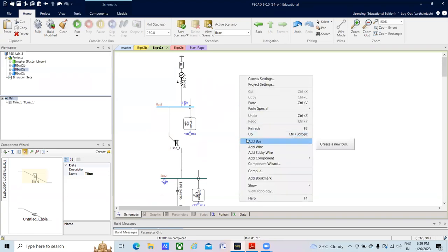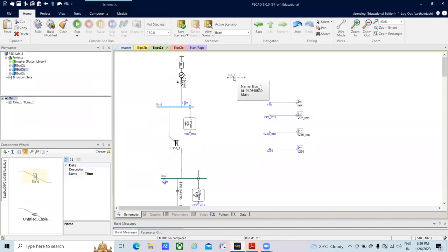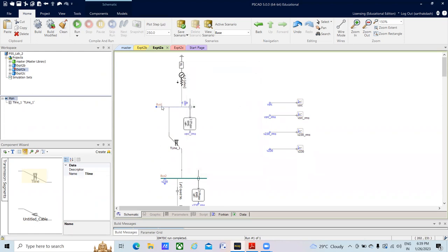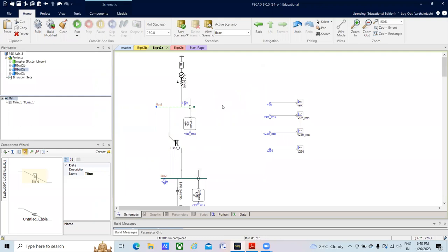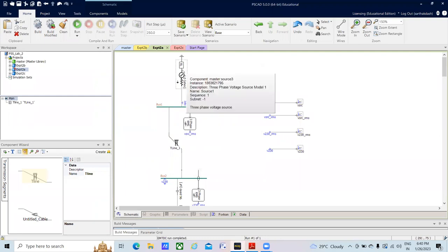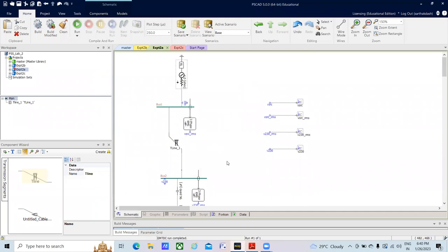To add a bus, right-click and select Add Bus. Double-click on the bus and set the base kV — it is better to set it to 230 since we are working on a 230 kV system. The voltage magnitude will be 1 per unit. The three-phase voltage source is from the Master Library. In the source control, set 230 kV and 60 Hz as parameters, and 100 MVA.